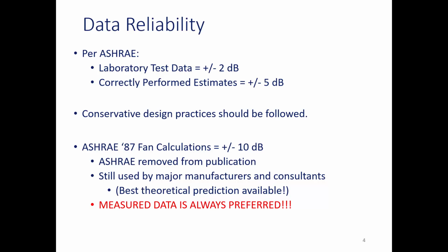And so they want to put the biggest rooftop units that they build - some of them might be in the hundreds of tons - they want to be able to put those in there and measure them at many different operating conditions, so that they can provide data to the acoustical engineer that will make sure the background noise criteria is met.